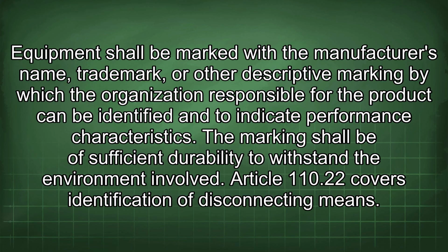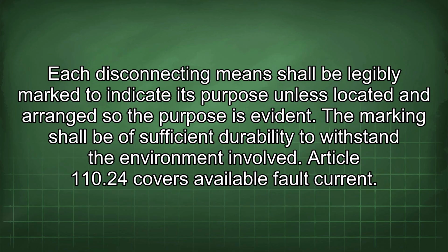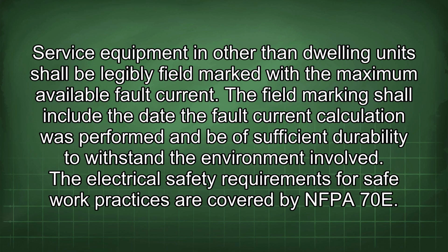Article 110.22 covers identification of disconnecting means. Each disconnecting means shall be legibly marked to indicate its purpose unless located and arranged so the purpose is evident. The marking shall be of sufficient durability to withstand the environment involved. Article 110.24 covers available fault current. Service equipment in other than dwelling units shall be legibly field marked with the maximum available fault current.